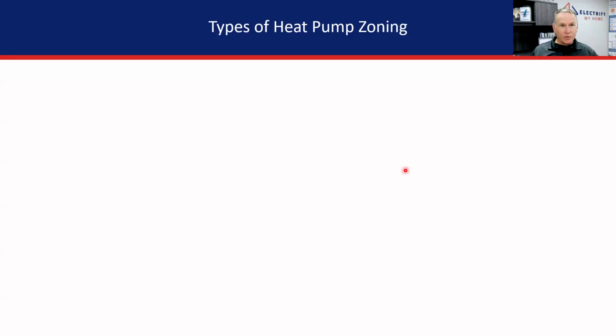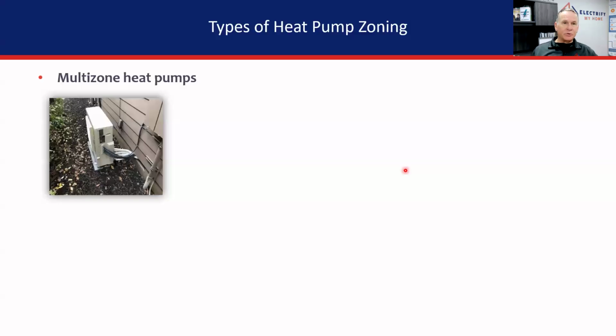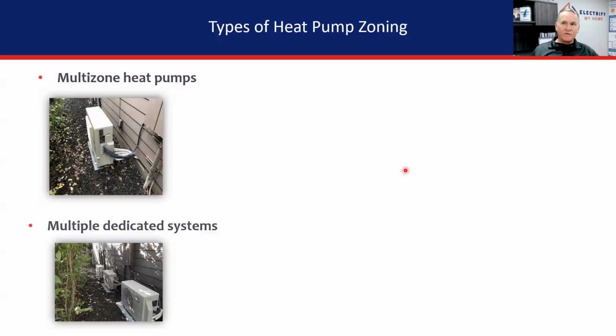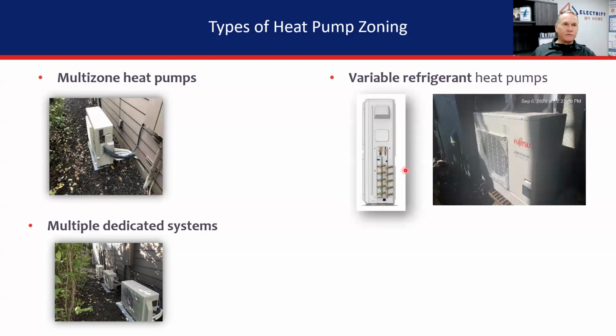Inverter heat pumps have helped with that a bit, and multi-zone technology has helped a bit, but we've got to be really careful with multi-zone. We'll get into the details about that. What we found is that with heat pump zoning, multiple dedicated systems work so much better, so we're going to share the reasons why. And then we have variable refrigerant flow. These are great because they have a really low turn down rate and they don't need to share refrigerant with the other circuits, so they have the best chance at real zoning. But these things are really expensive and way more difficult to install, and they're pretty difficult to install on an existing home, like a retrofit scenario.